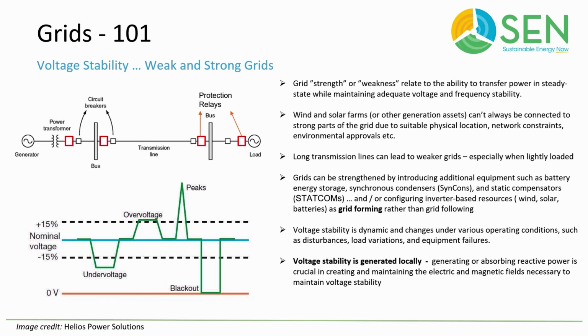Voltage stability is very dynamic, and the system response changes under various conditions such as disturbances, load variations, and equipment failures. Now, a key point about voltage stability, unlike frequency control, is that it's actually needed locally. So it's got to be done locally, and this involves generating and absorbing what's called reactive power.